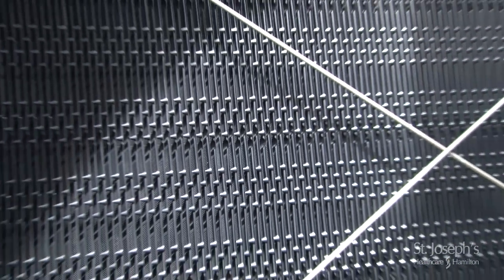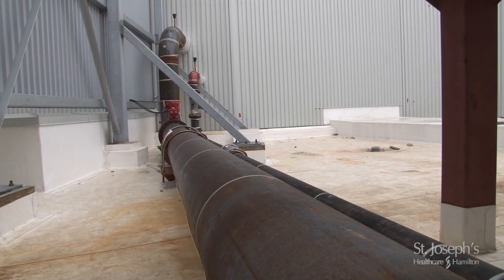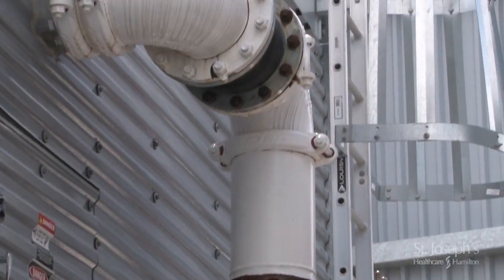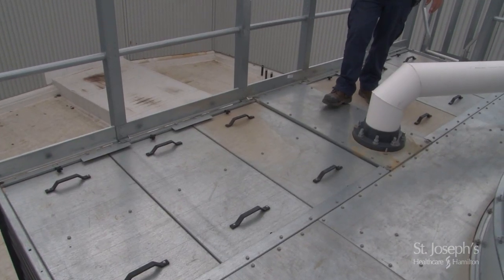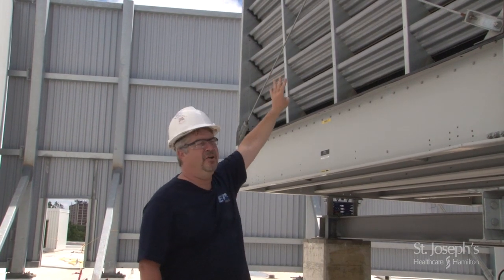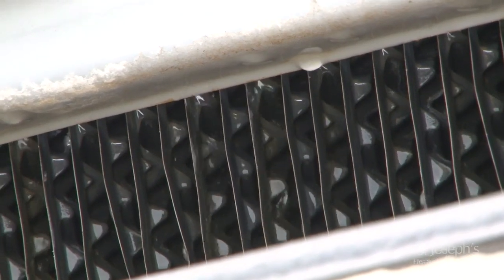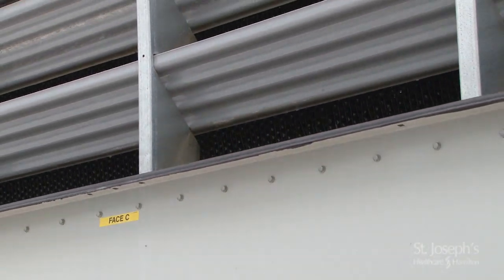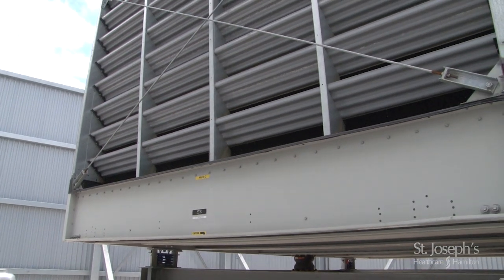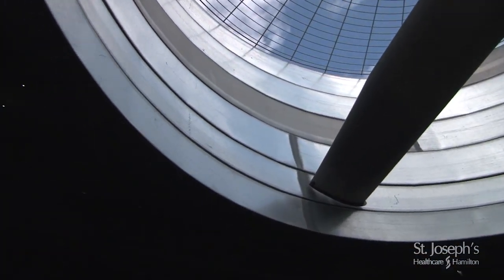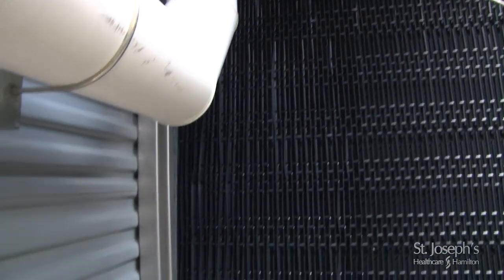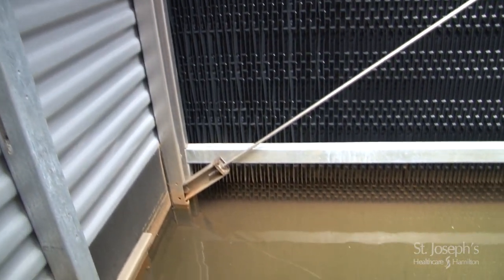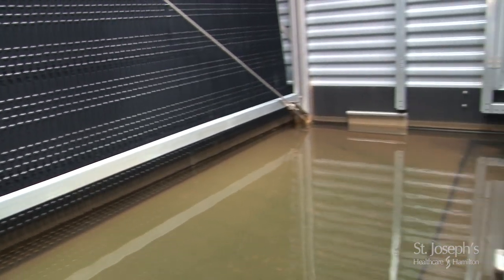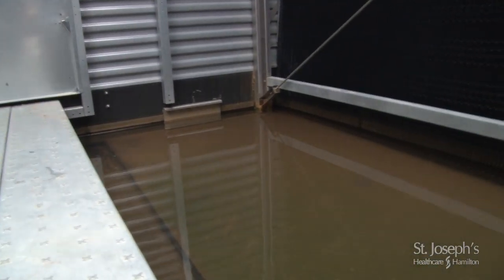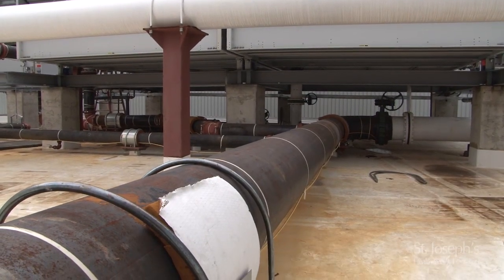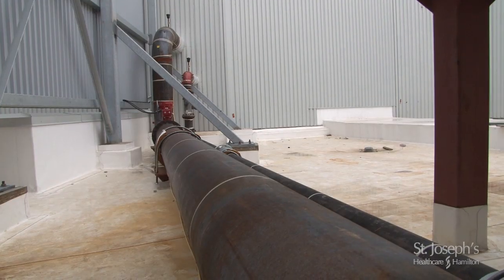How a cooling tower works is warm water from the building will flow from inside the building and is pumped up to the top of the cooling tower. It fills hot water boxes in the top, and that water is then cascaded down through these black PVC fill packs. As the water's cascading down, the fan on top is pulling outside air in through the louver face and cooling that water down. That water then lands in what is referred to as a cold water basin. It is then drained back down through that pipe at the bottom of the tower and is returned back to the building, to the chillers, and the whole cycle starts over again.